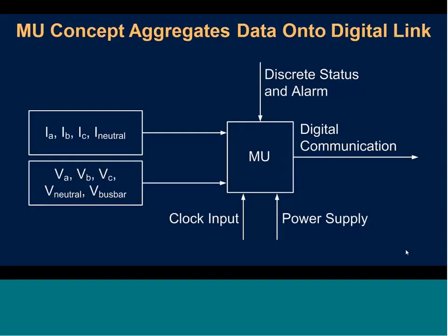So I've used the term merging unit a little bit before, but just for some clarity, what exactly are we merging? The idea is we're merging both current and voltage signals, I/O, discrete status, as well as a clock input. We need some kind of way to align our data. All of that is combined into a single unit and then sent out through a digital communication link. So the merging unit in the next couple slides is what would be out in the substation yard.